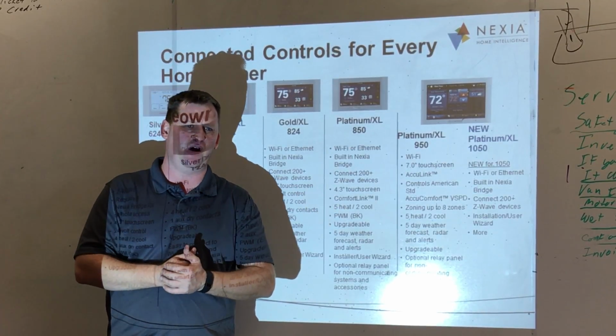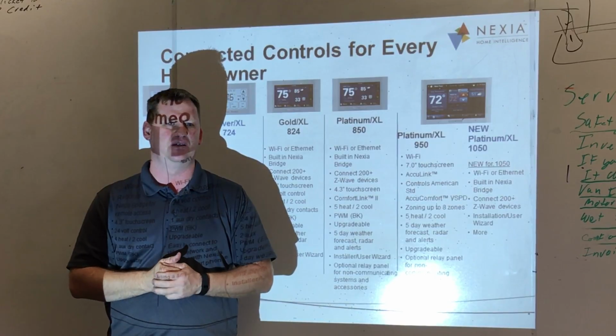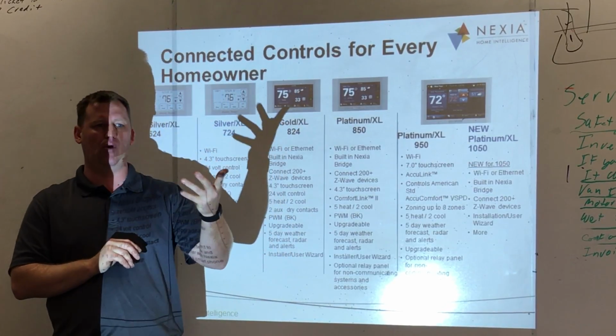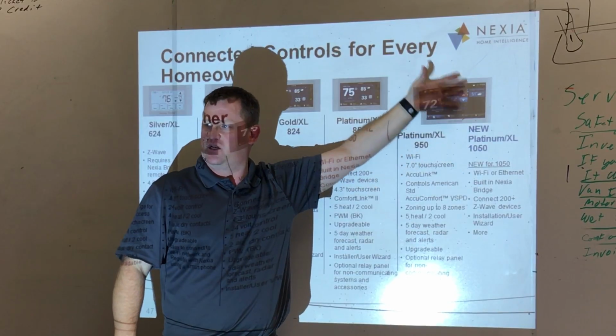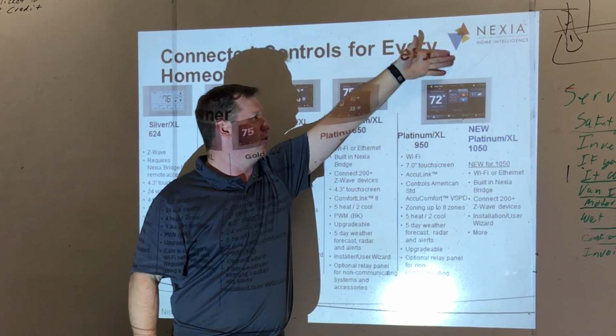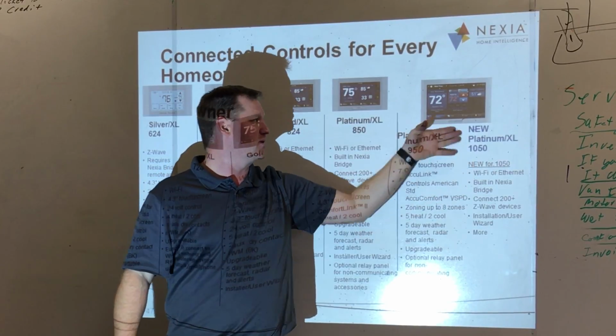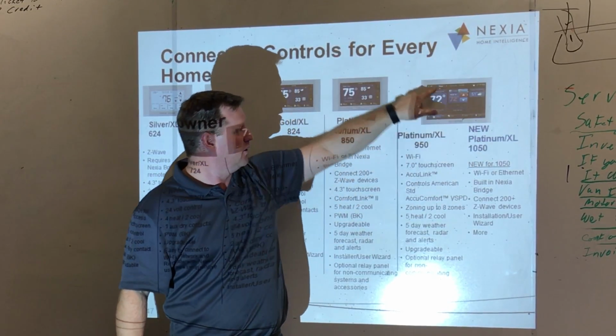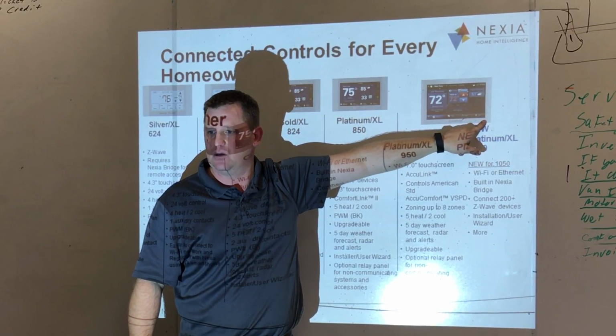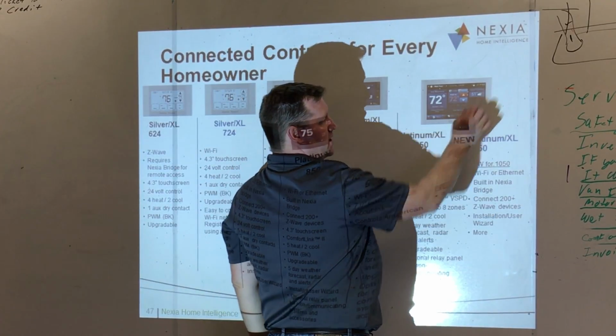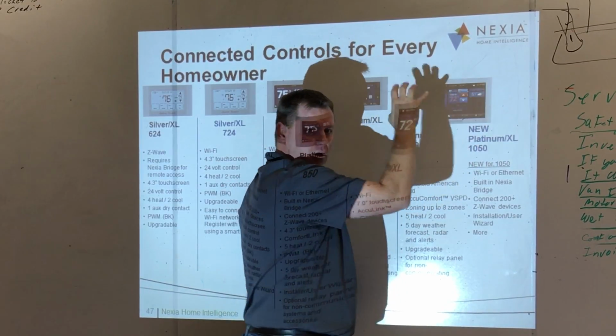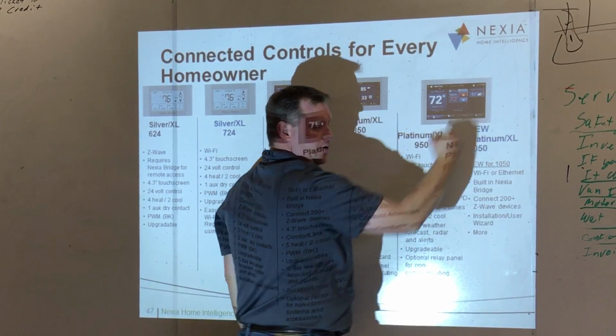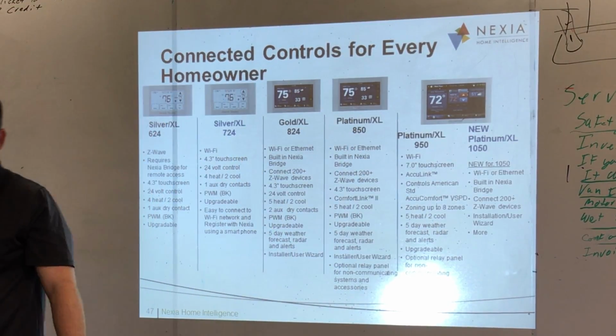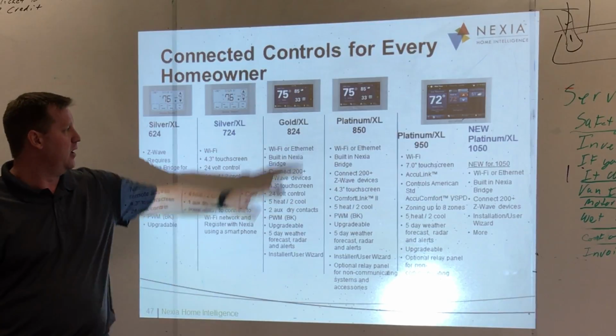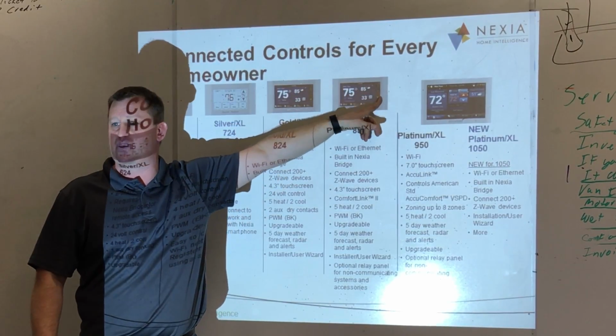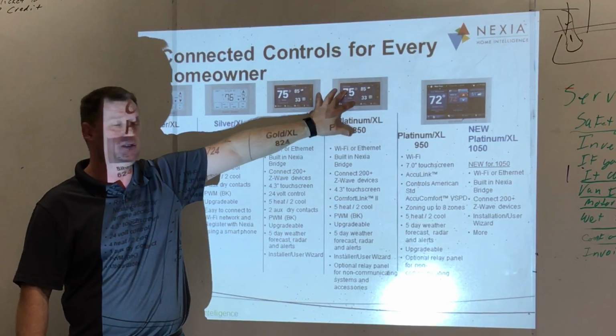There was a return right below the stat on the floor, so whenever the blower ran, it would start pulling air differently and affect the sensor - air would run down the face of the stat instead of letting heat naturally convect. The processor is here, the temp sensor is here, so on the new 1050 the sensor will be external to the control board area, on the side. I can show you pictures of mine at home. That'll help take care of the issue, and we're going to do the same redesign with the 824 and 850 later this summer.